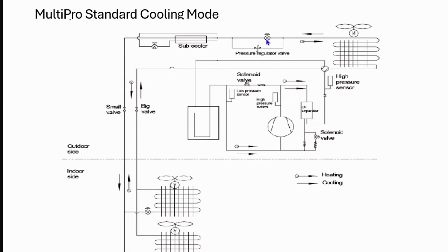This outdoor heating EEV, so if we were in heating mode, that is my EEV for heating mode, and is going to meter my refrigerant into the outdoor coil in heating mode, because now this became my evaporator. These two coils become condensers. Okay, so at that point, we are flashing refrigerant this way. But if we were in cooling mode, that EEV has got to be all the way open.